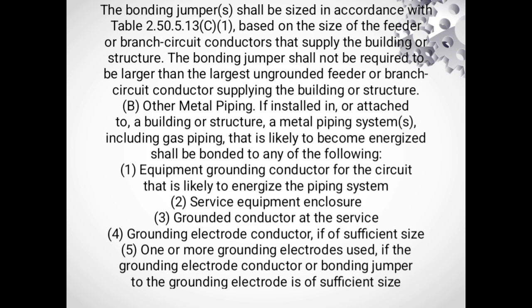Other metal piping. If installed in or attached to a building or structure, a metal piping system including gas piping that is likely to become energized shall be bonded to any of the following. Number 1. Equipment grounding conductor for the circuit that is likely to energize the piping system. Number 2. Service equipment enclosure. Number 3. Grounded conductor at the service. Number 4. Grounding electrode conductor if of sufficient size. Number 5. One or more grounding electrodes used if the grounding electrode conductor or bonding jumper to the grounding electrode is of sufficient size.